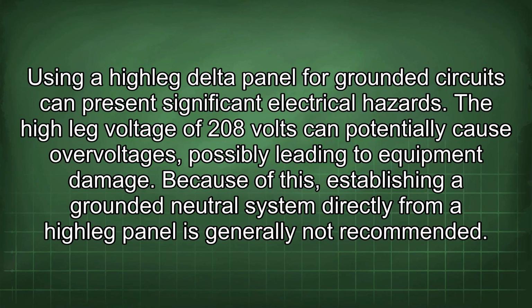Using a Highleg delta panel for grounded circuits can present significant electrical hazards. A high-leg voltage of 208 volts can potentially cause overvoltages, possibly leading to equipment damage. Because of this, establishing a grounded neutral system directly from a Highleg panel is generally not recommended.